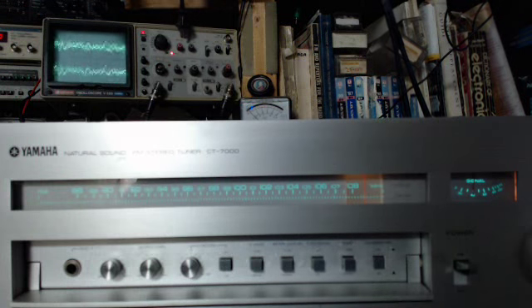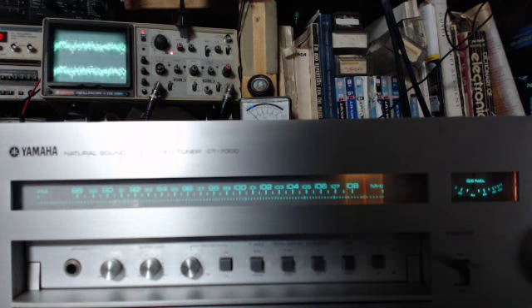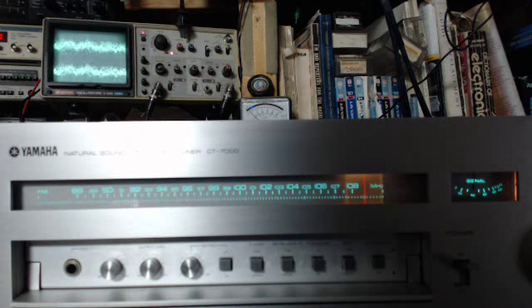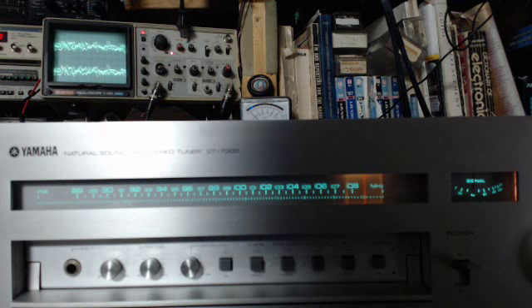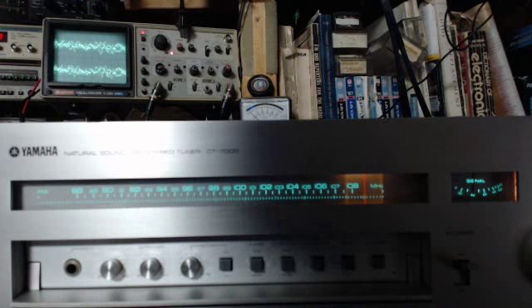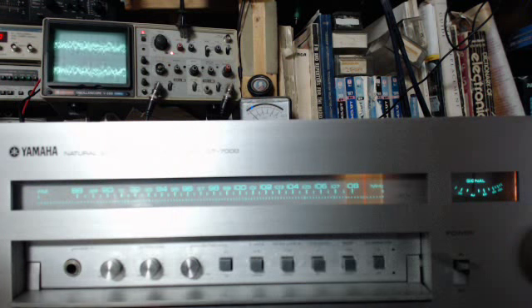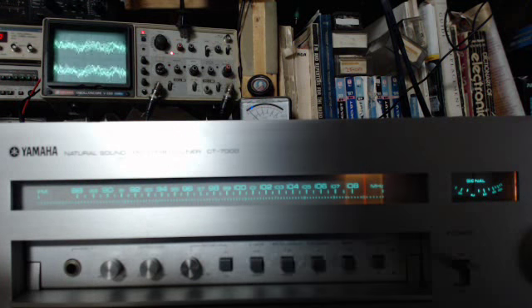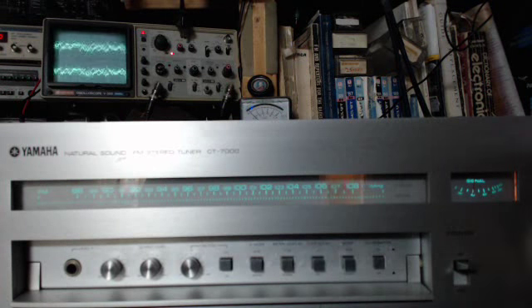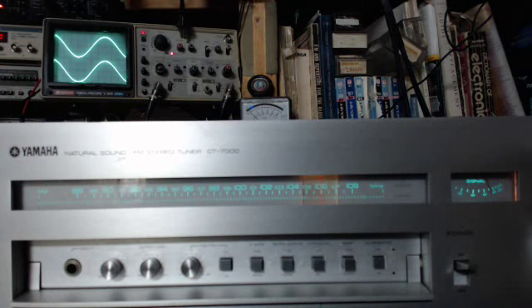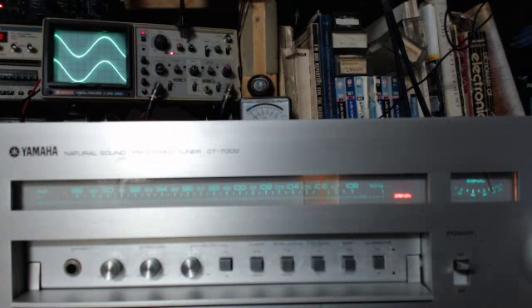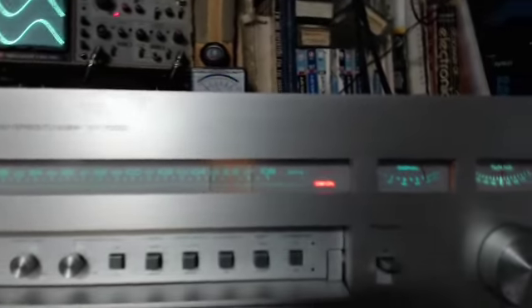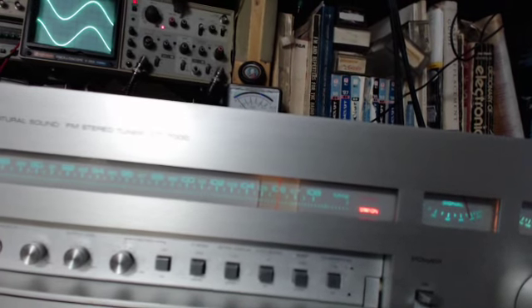What I'm going to do is push the button on the generator for 106, which is the upper-end dial calibration point. We're going to go up to 106, and see just how close the dial calibration is. Right on the money. I'm going to zero in on that. I'm going to zero in on that to show you that it's on 106. The red dot, the red vertical line is on 106.